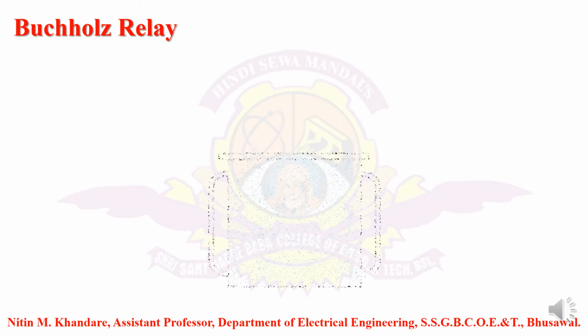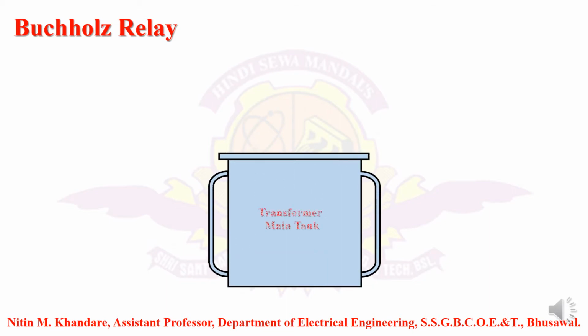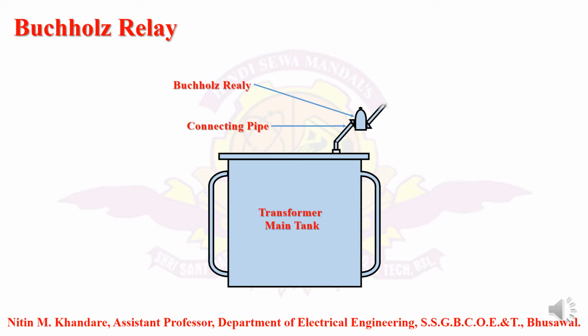Conservator tank is the tank which is used for maintaining the oil level in the transformer tank as 100%. So, there's the transformer tank which is connected with a connecting pipe which is further carried to the conservator tank, but in between the main tank and the conservator tank we are connecting the Buchholz relay here. That is, the output of the Buchholz relay, that is the second terminal of it, is connected with the conservator tank. So this is the simple construction as well as the location of the Buchholz relay.